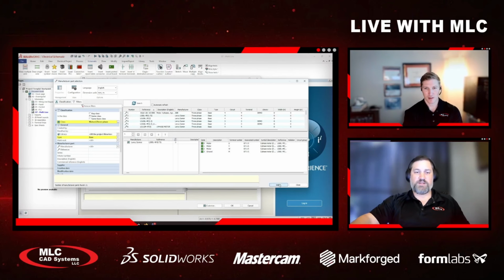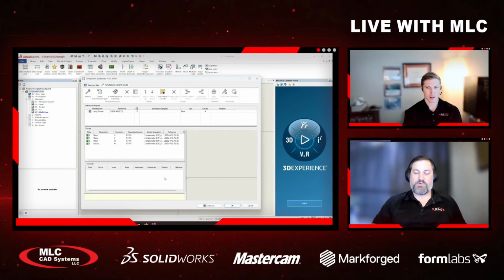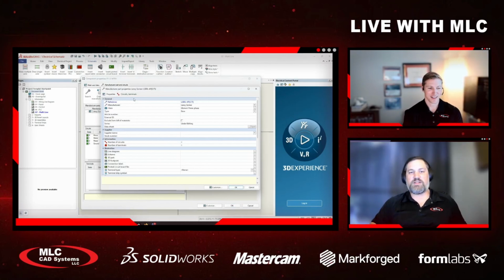When I do that, I'm telling the software, "Hey, I know that I put a generic three-phase motor down, but it really means this specific manufacturer part." Just like if you were to go to procurement and the order entry team, you say, "Hey, I need a breaker." They're going to say, "What part number?" Yeah. So that's what we're telling the software here, what motor this actually is. When I click on this and hit properties, you'll see kind of where the rubber meets the road. So this is the part number that we're going to list in our bill of material now.